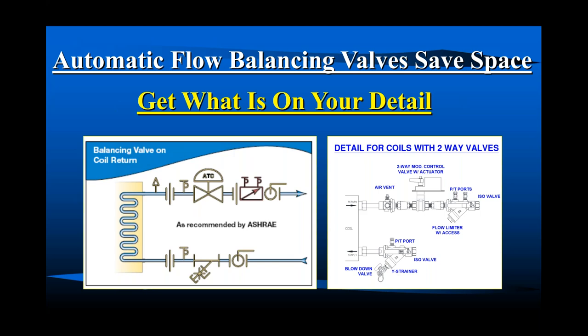Get what's on your detail. So this is the recommended detail by ASHRAE. Kind of a basic isolation valve, strainer with blowdown, PT port, union. And there it is right there: isolation valve, strainer, blowdown, PT port. There's a union in one valve body. Hard to run out of room. Same on the return side.